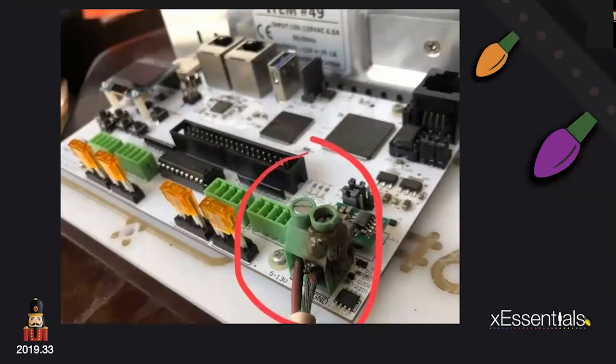Most of you would have seen this pop up on one of the Facebook groups the other day. You can see here, and what we can tell from having the discussion with the person who posted this, was the screw was loose, it wiggled loose. So it was arcing, jumping, melting. So that's a very expensive fix now. You've got to unsolder that. Hopefully nothing else has been too badly damaged further down the line, and you've got to replace it.